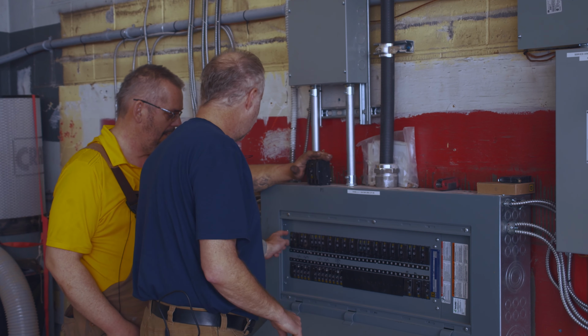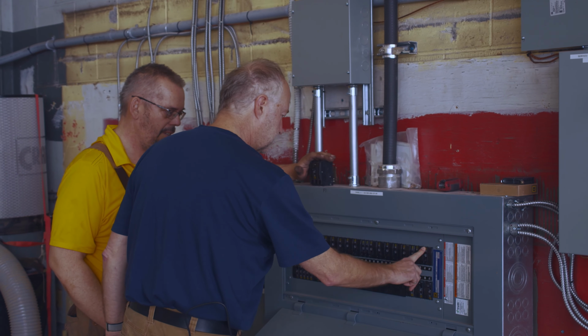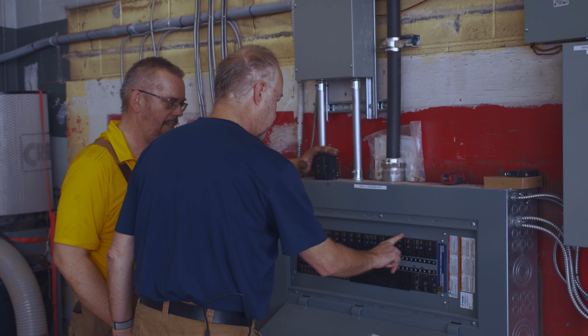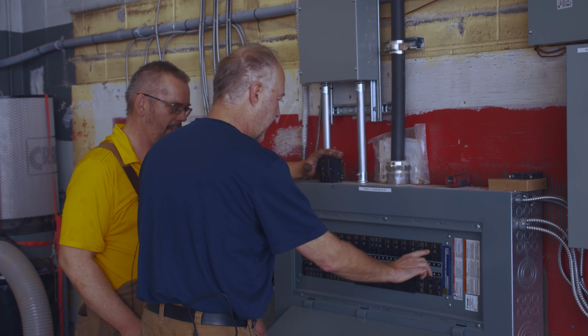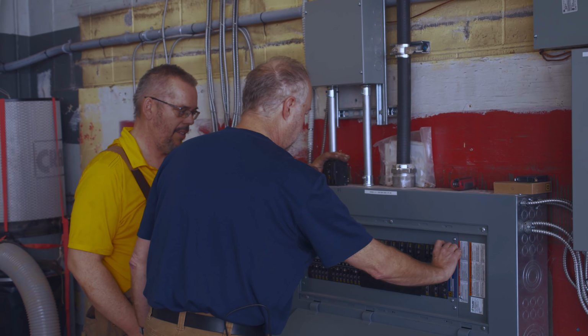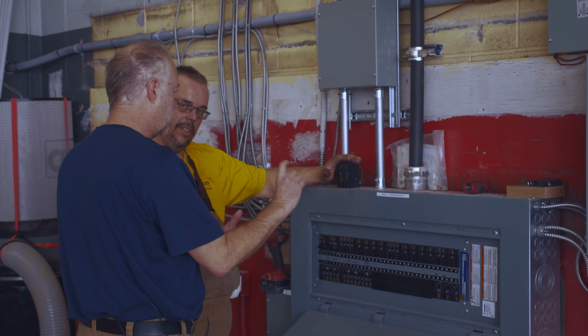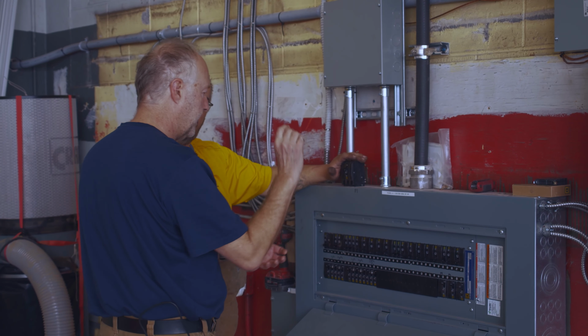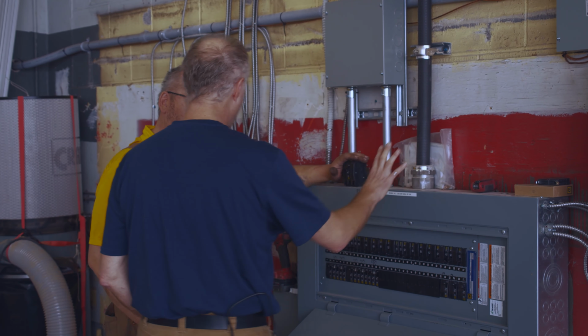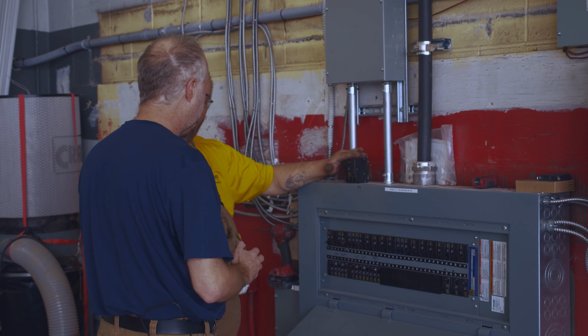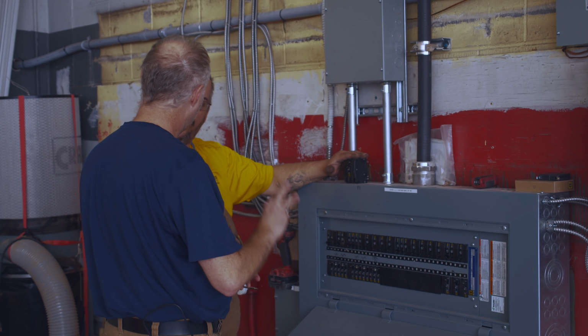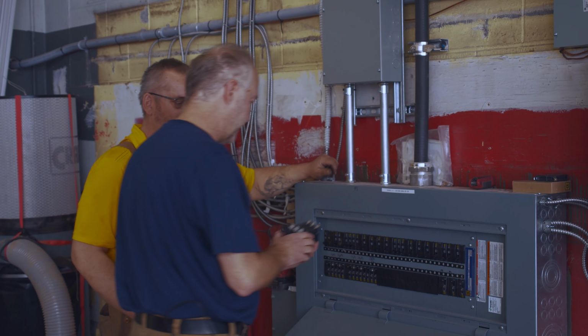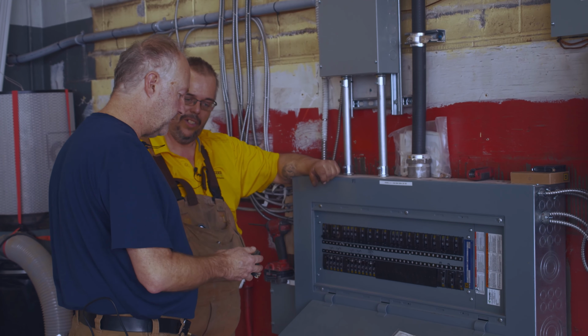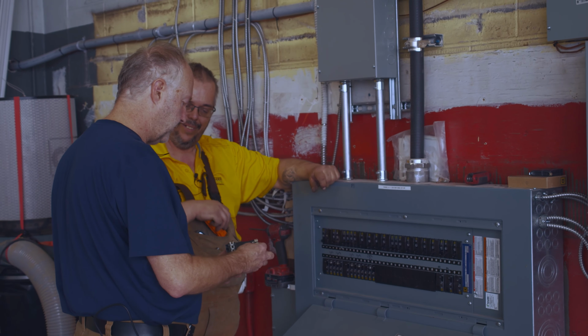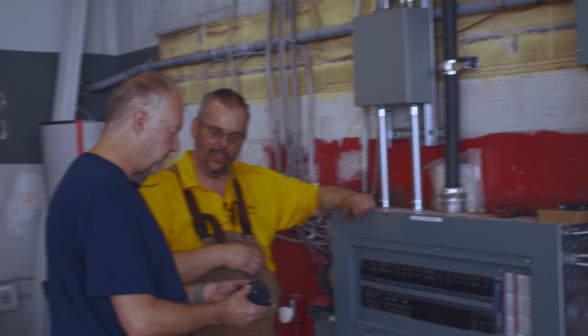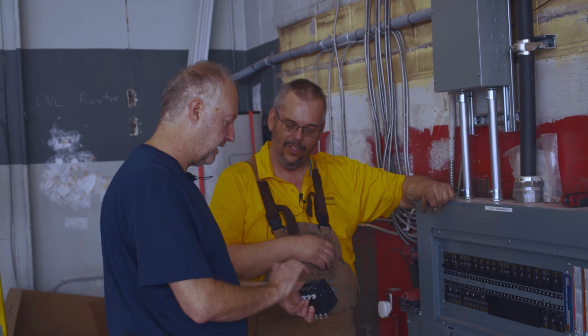But then they actually go one phase, 2, 3, 1, 2, 3, 1, and so if you put in a single breaker, the way 208 works is you get your 120 volts out of there. Yes. And then you put two of them in, you get your 208 volts. Yes. But if you put three of them in, you still get 208. You just get three-phase power for motors. So this is an example of a three-phase, three-pole breaker. It's like three breakers kind of glued together, but you can get your three-phase power out of here.